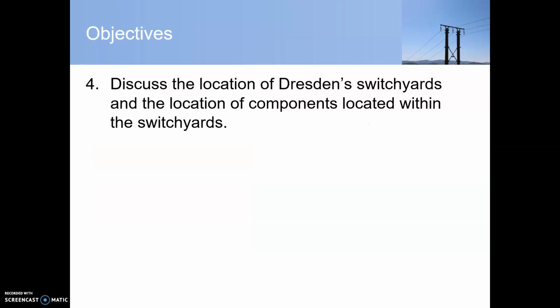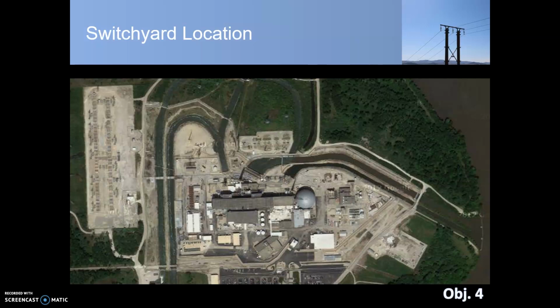Our objective for this module is to discuss the location of Dresden switchyards and the location of components located within the switchyards. This is a satellite view of Dresden Station. If you remember back to Objective 1, we said that Dresden had 3 switchyards, and they were divided based on voltage. Our 345 kV switchyard is located on the west side of the property. Our 138 kV and 34 kV switchyards, which are connected together, are located on the north side of the property.